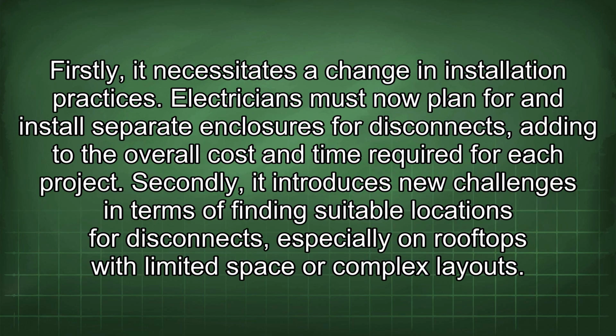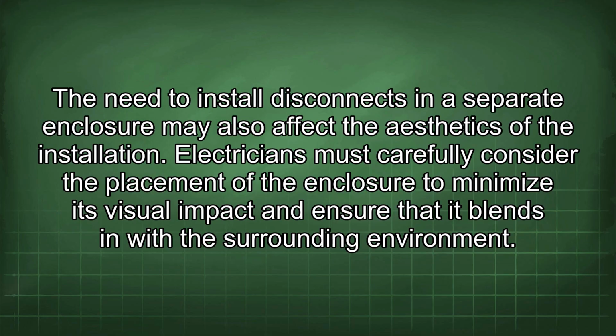Firstly, it necessitates a change in installation practices. Electricians must now plan for and install separate enclosures for disconnects, adding to the overall cost and time required for each project. Secondly, it introduces new challenges in terms of finding suitable locations for disconnects, especially on rooftops with limited space or complex layouts. The need to install disconnects in a separate enclosure may also affect the aesthetics of the installation. Electricians must carefully consider the placement of the enclosure to minimize its visual impact and ensure that it blends in with the surrounding environment.